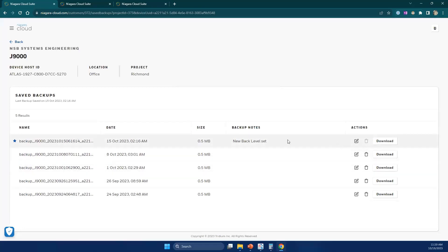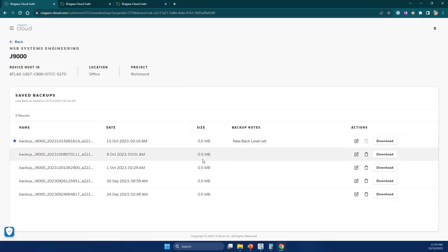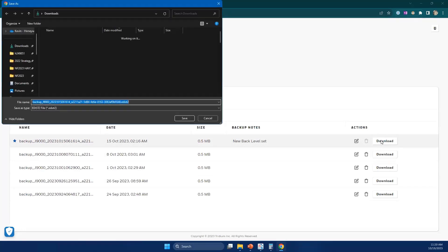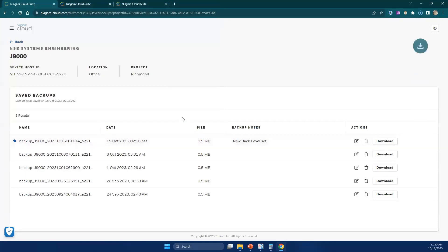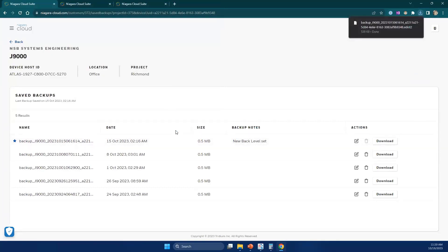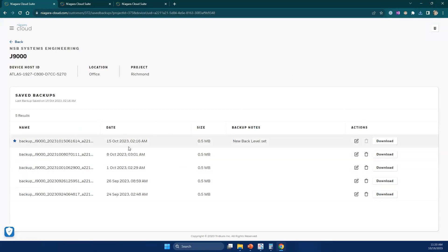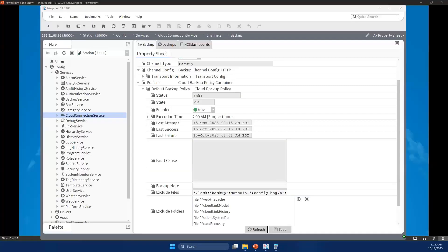I can mark a backup as preferred, meaning it will never be deleted. The other four will round-robin, so every Sunday you'll see a new backup come in. From here I can download a backup — I'll click download, it goes to my downloads folder. One important thing Nicole mentioned and I'll reiterate: it is encrypted with the actual passphrase of the JACE. If you're used to installing dist files from a backup, there's one extra step you'll have to do to restore it to that JACE.